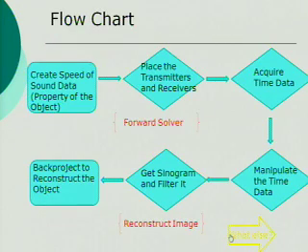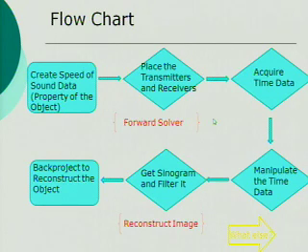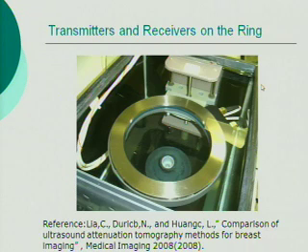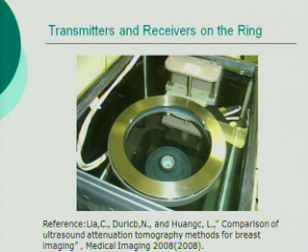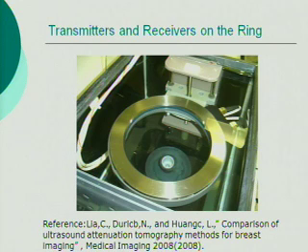After we have the speed of sound data, we can place the transmitter and receivers in order to acquire time data. This is a real experimental setup. On the ring, there are 256 transmitter-receiver sites. Each transmitter transmits a sound wave to all the receivers, and the receiver acquires time data for the path that the sound wave propagates through. The object is in the middle of the ring.